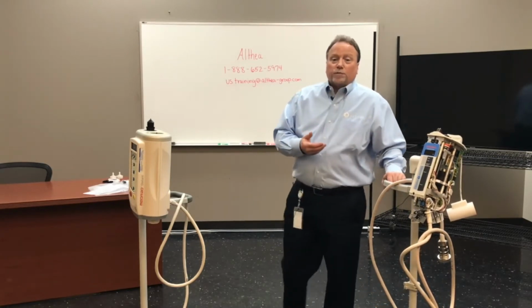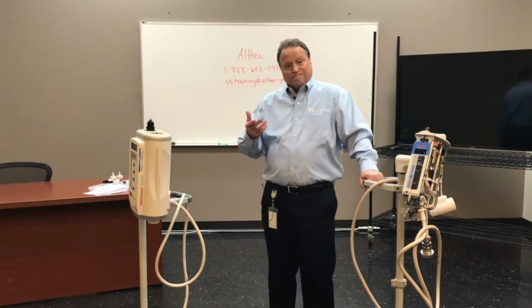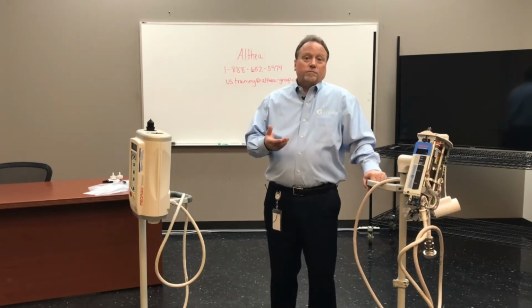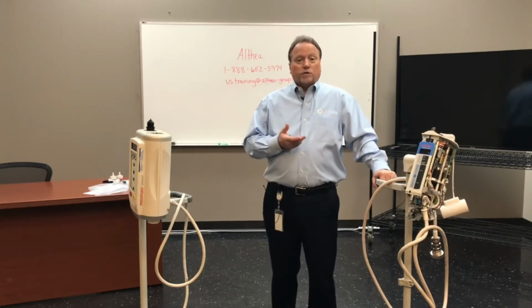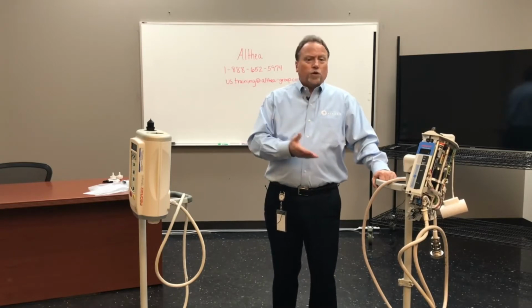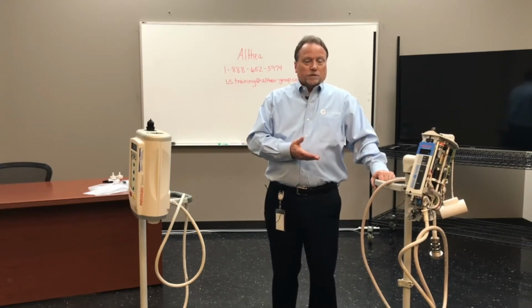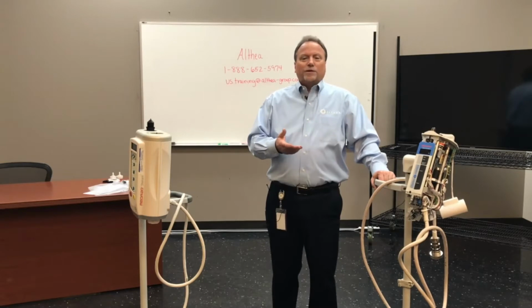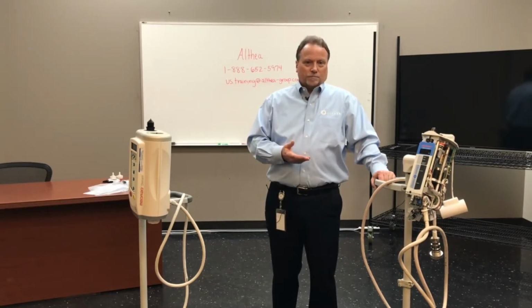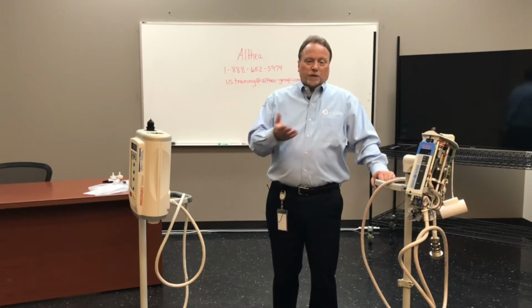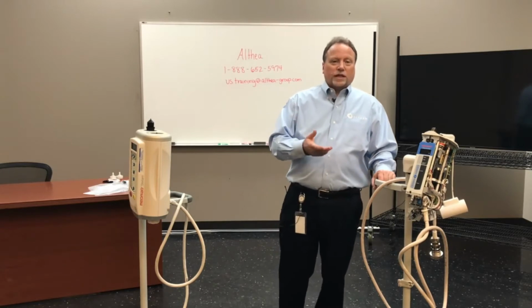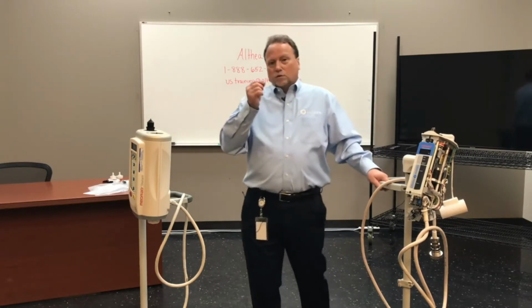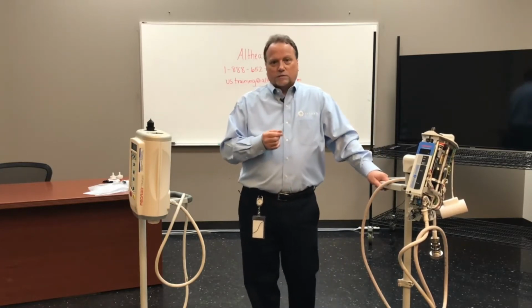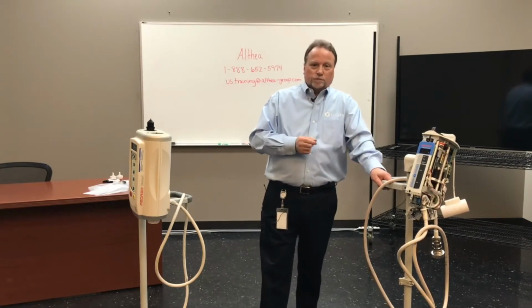Do you have to replace every gasket? Well, you're in there. You have to take the covers apart. So why wouldn't you replace the gaskets? Does it take extra time? Minimal amount of time. Don't be lazy and say, well, I'll just get it next time. Just remember, with contrast on them, the gaskets are no longer good.